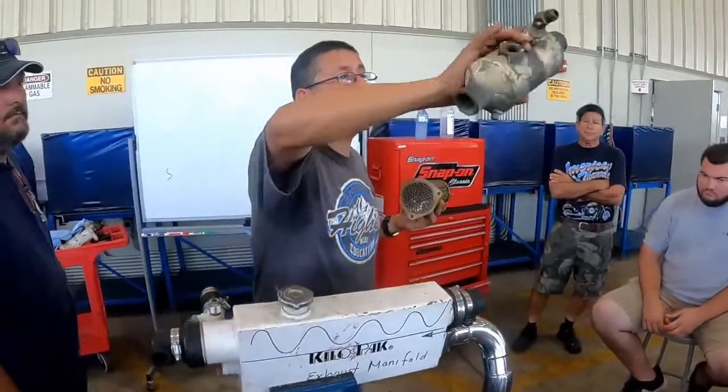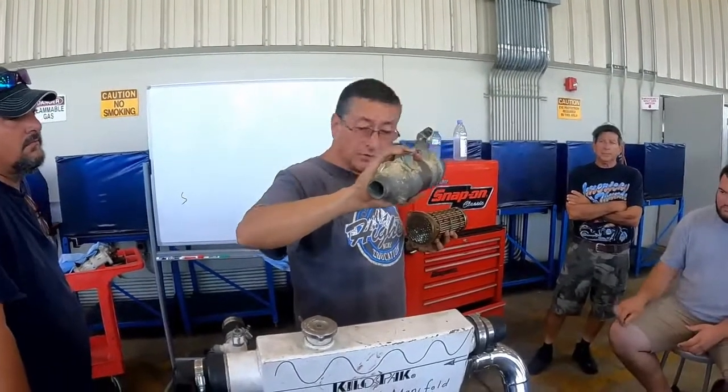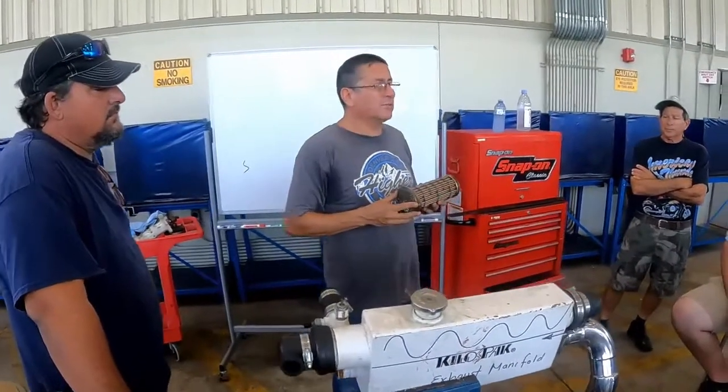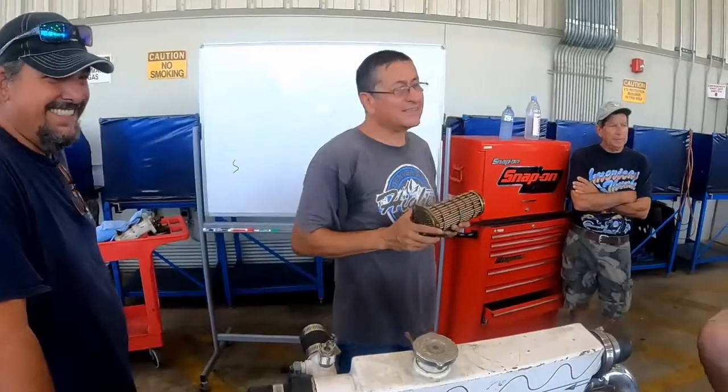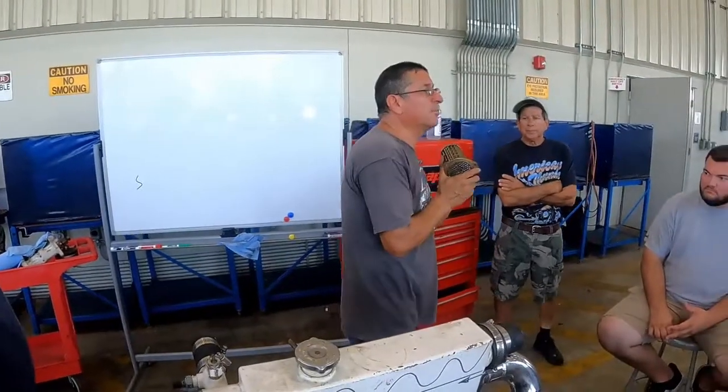Can I send this element to the machine shop and they test it at high pressure? Yes. But they can't fix it if one of those pipes has a hole in it. In some shops, they fix it, as long as it's not the one in the middle. Is that expensive? Papi, this part? It's too expensive because it's nickel copper 90/10.